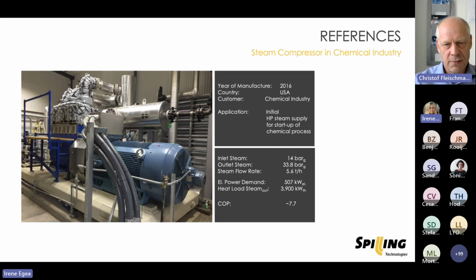So therefore, we need 2 stages here, although the compression ratio is only about 2 point something, so it's not that high. But the steam always becomes hot during compression, and since we even start at quite a high temperature level, we have to do it in smaller steps. Here we reach a COP of about 7.7. Okay, next slide.